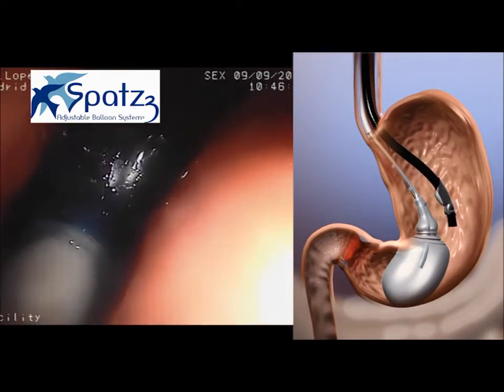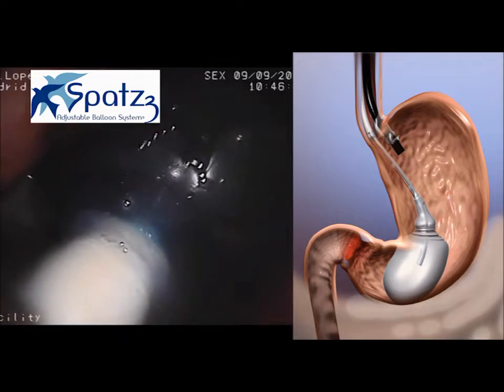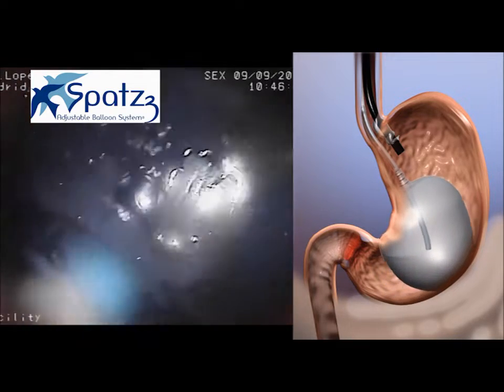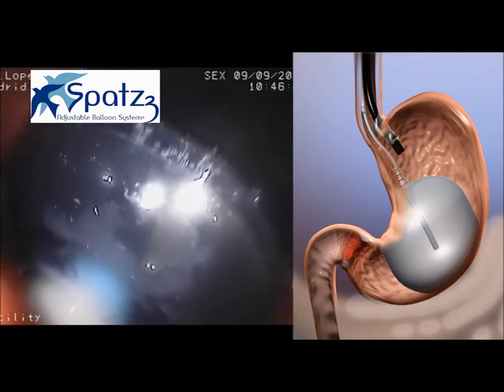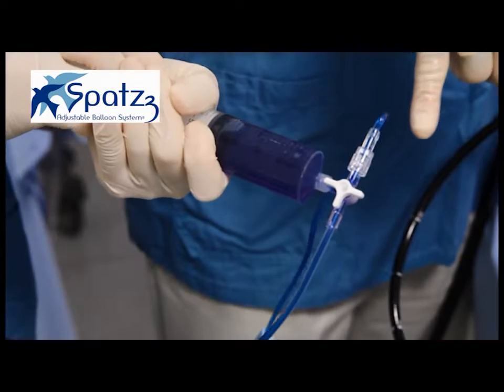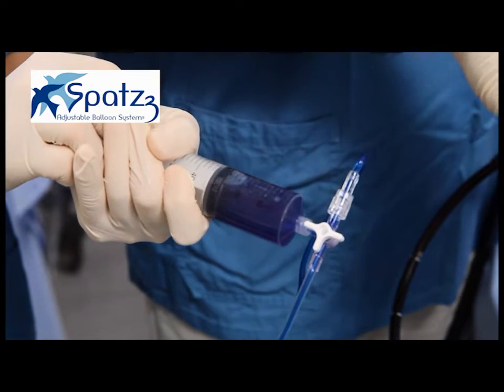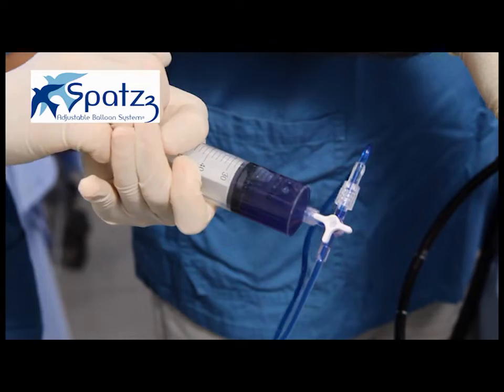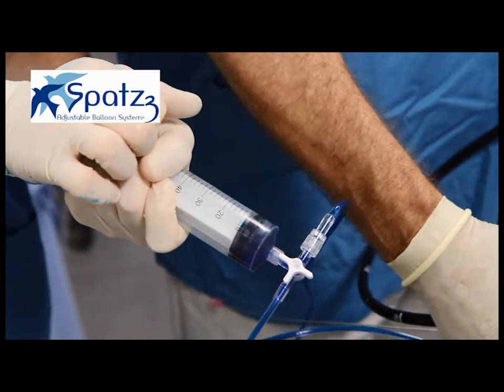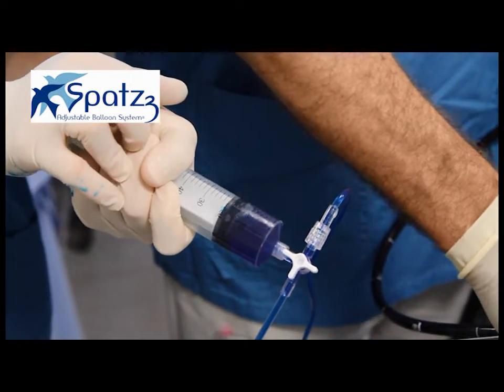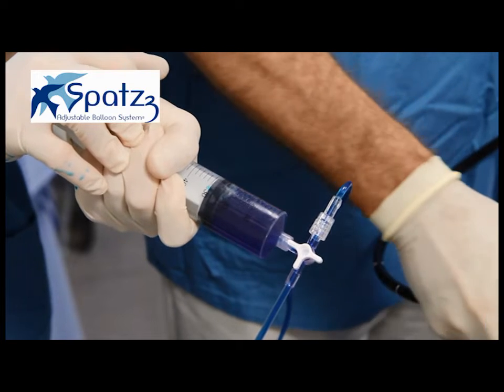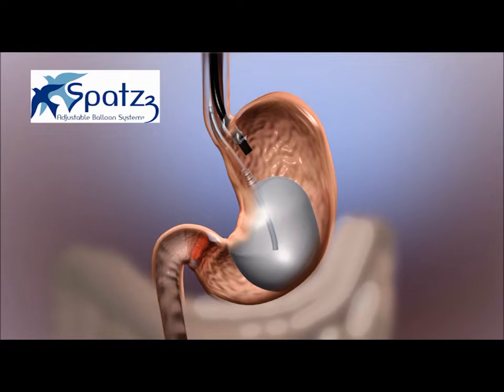Pull the endoscope back to confirm release of the balloon. A completely filled balloon will have no creases and will have a thick cap. Once fully inflated, the balloon can be inflated further or deflated to the desired final volume. We recommend 550 to 600 cc as a starting point, since it can be adjusted upward at a later date.